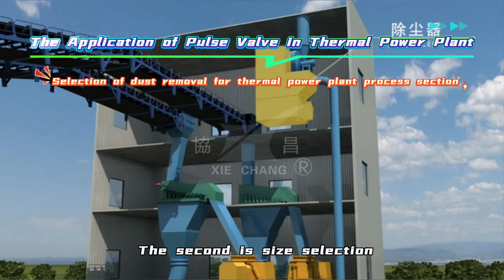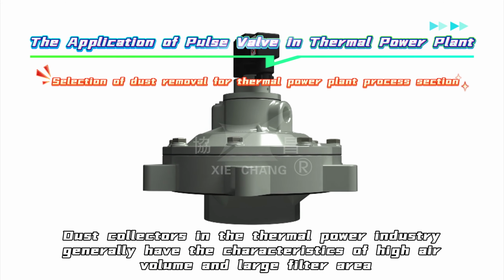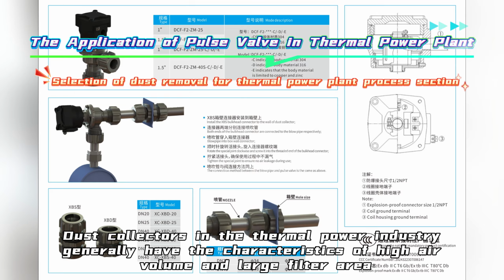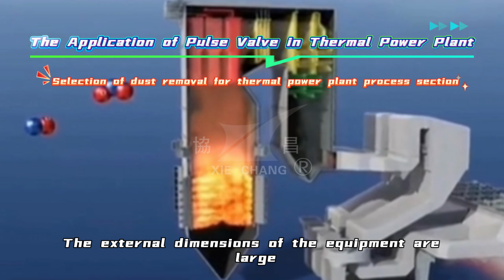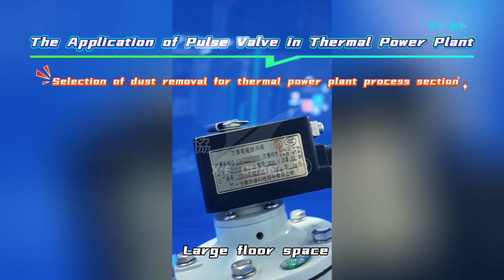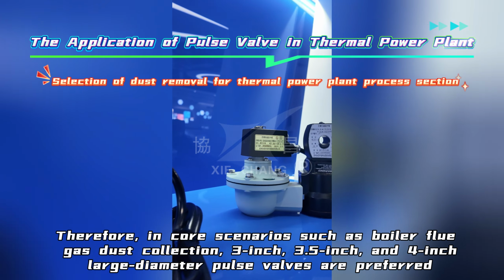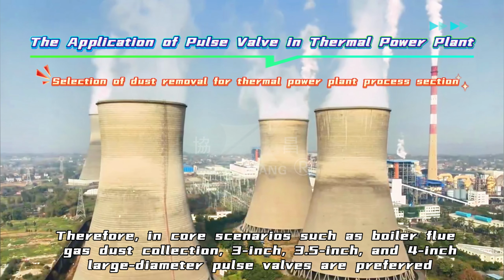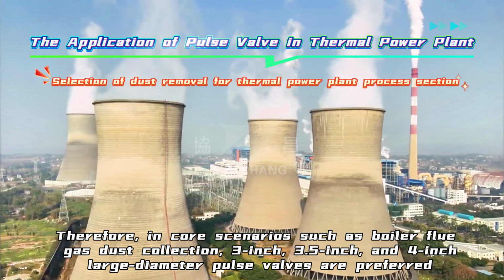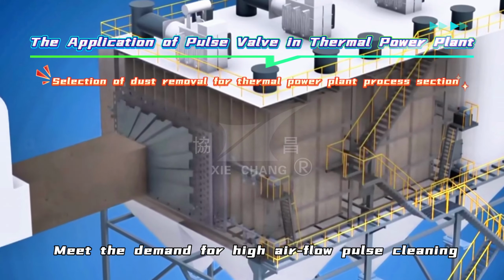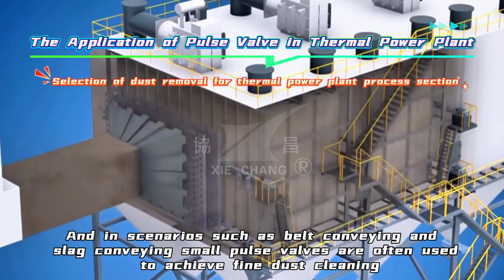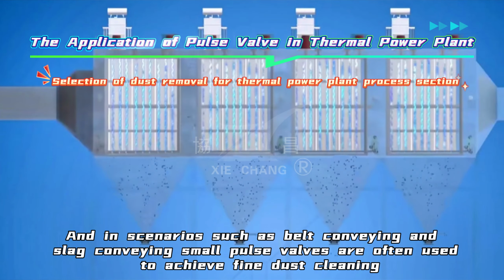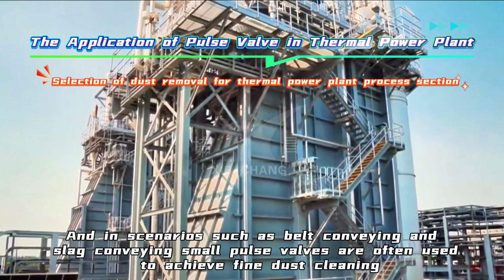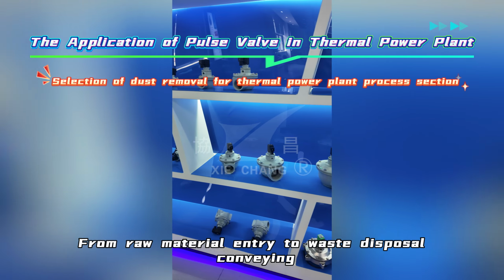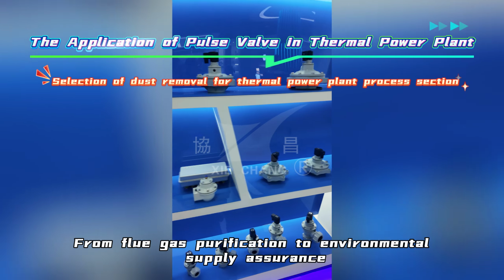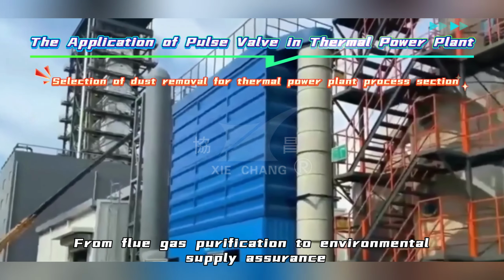The second is size selection. Dust collectors in the thermal power industry generally have the characteristics of high air volume and large filter area. The external dimensions of the equipment are large, with a large floor space. Therefore, in core scenarios such as boiler flue gas dust collection, 3-inch, 3.5-inch, and 4-inch large diameter pulse valves are preferred. Meet the demand for high airflow pulse cleaning. And in scenarios such as belt conveying and slag conveying, small pulse valves are often used to achieve fine dust cleaning.